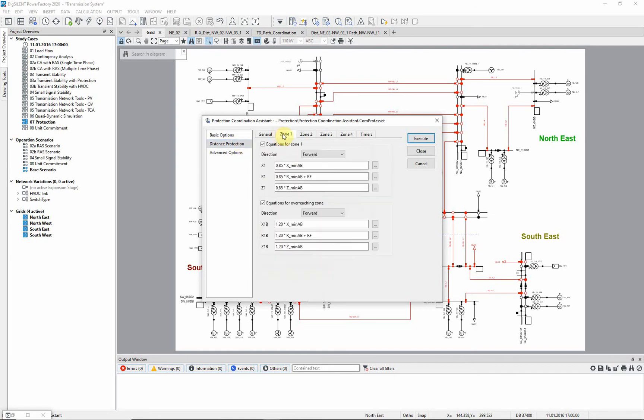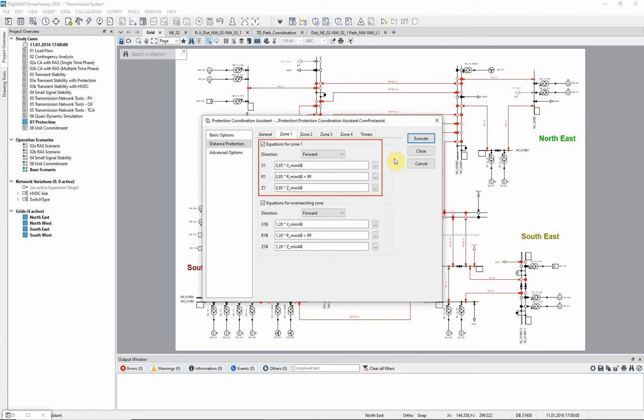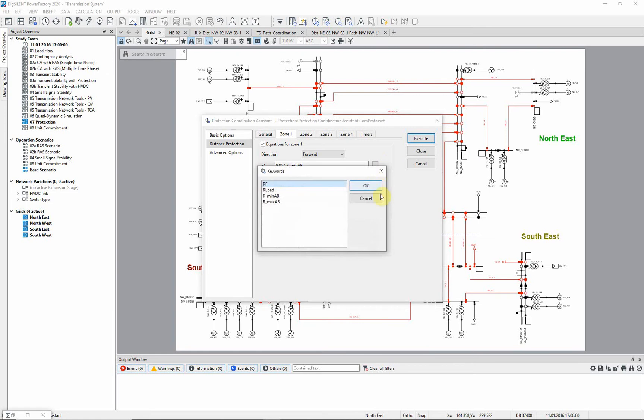In the following tabs, the equations for four zones can be defined. Equations for zone 1 are straightforward and take 85% of the shortest line to determine the settings. In addition, the fault resistance variable is added to the resistive reach. Possible input variables can be accessed here, next to the equation field.